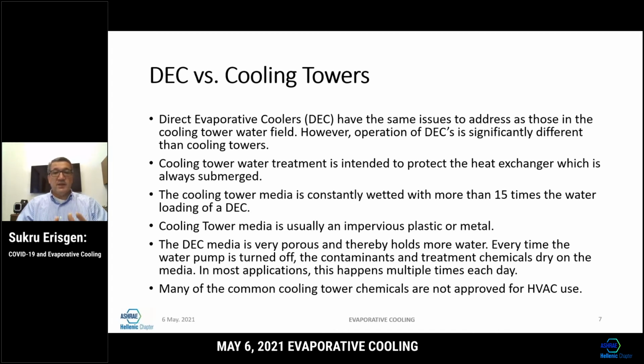Therefore, cooling tower media can be made out of plastics and metals because they can resist chemicals, as opposed to the media used in direct evaporative cooling. Direct evaporative media is very porous and holds more water, and, as I mentioned, the chemicals.